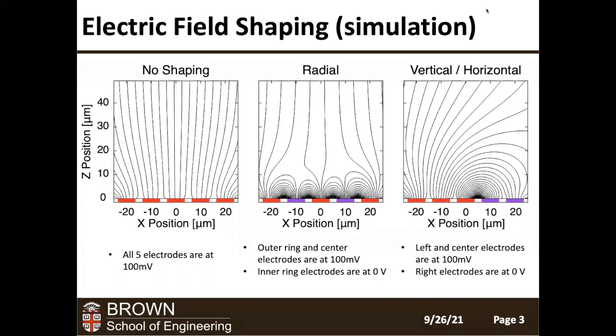EIS measurements are fundamentally measuring the local electrical environment around each pixel. When the electrode area is small and at high measurement frequencies, much of the electrical response is actually in the fringing field, extending outward from the pixel. And once we have a dense array of microelectrodes, those fringing fields are influenced by all of the neighboring pixels. Here is an example of electrostatic simulation showing how the electric field is affected by the bias applied to other nearby electrodes. These multi-electrode patterns offer a new opportunity to shape the applied electric fields and therefore change the sensitivity of the EIS imaging sensor.